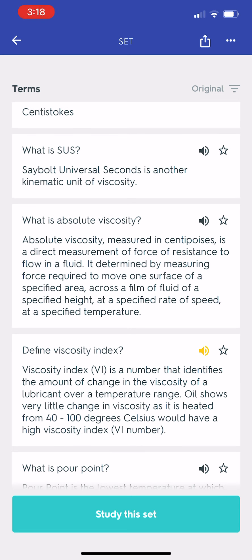Define viscosity index. Viscosity index is a number that identifies the amount of change in the viscosity of a lubricant over a temperature range. An oil that shows very little change in viscosity as it is heated from 40 to 100 degrees Celsius would have a high viscosity index.